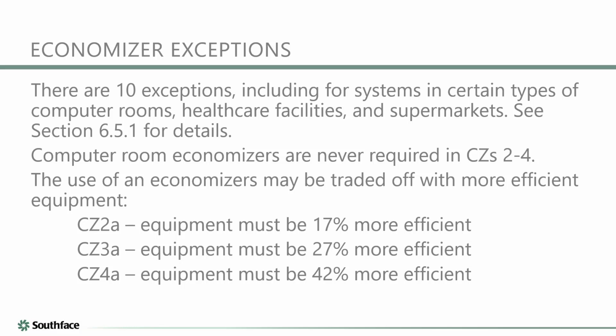because you end up with a lot of those shoulder months where the weather is nice outside. So Hugh, when I hear you say this and sort of looking at these requirements and thinking through it, looking at these climate zones and the percent efficiency if you want to get out of the economizer mode, I probably think a simpler system, a building that has a couple split systems in climate zone 2 or climate zone 3, probably would look and go, yeah, maybe I'm just going to do more efficient equipment. I can get a 19 SEER heat pump pretty readily, and maybe that lets me hit this spec.